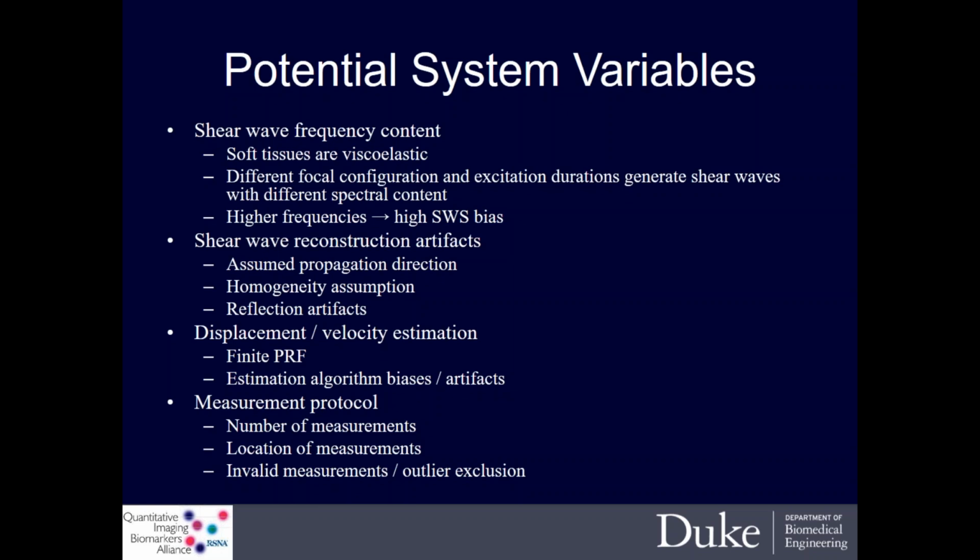We also know that shear waves could encounter structures and be reflected back into our regions of interest. We know that there's limitations on how finely sampled spatially and temporally shear waves can be reconstructed. And there was also potential protocol variability in the number of measurements used, where they were taken, how outliers were dealt with. All of this gave us a potpourri of topics to investigate.